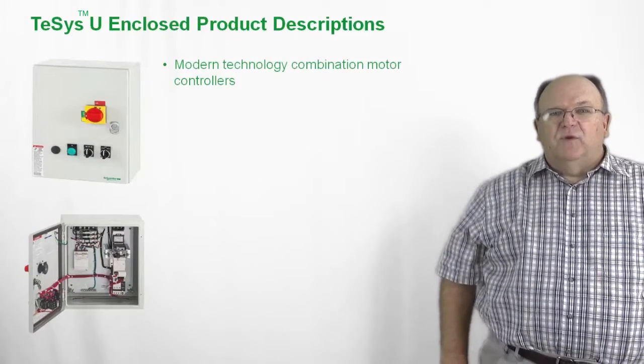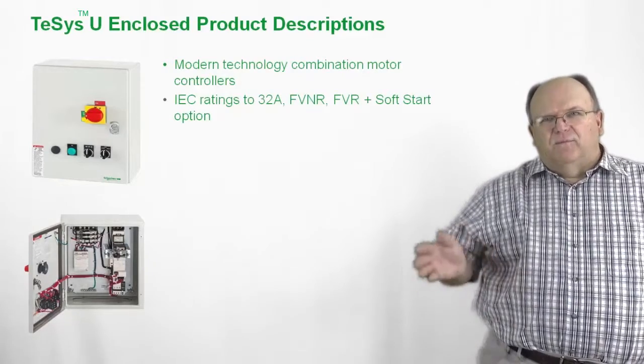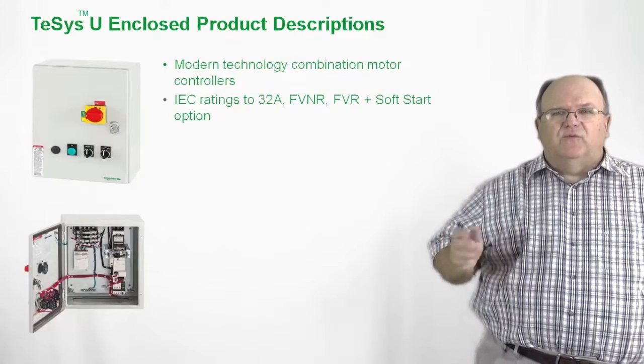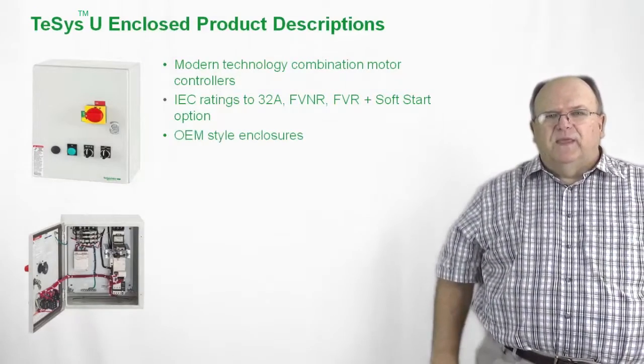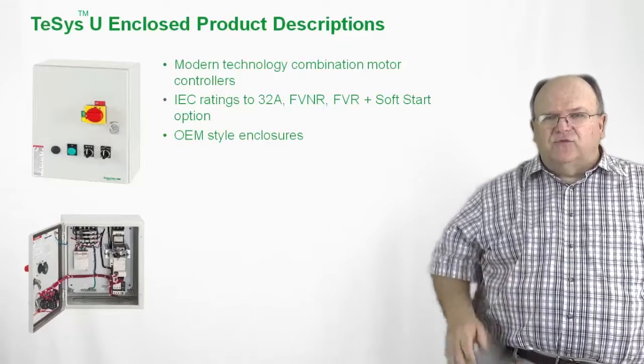Let's take a look at another option for the TeSys U. We now have an enclosed variation of the product available for our OEM and industrial customers. What we've done is used an OEM-style enclosure for the TeSys U that utilizes a rotary-type through-the-door operator. The product is available with all of the IEC ratings up to 32 amps — that's up to 20 horsepower at 480 volts — for both full-voltage non-reversing as well as reversing. We even have a soft starter option available for the enclosed version. The enclosure is very compact in size, with lots of available space for the OEM customer to add additional equipment inside the control cabinet.